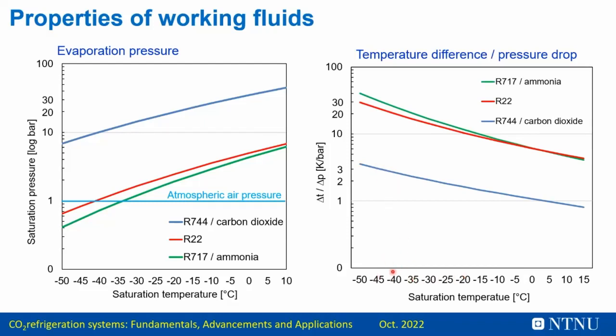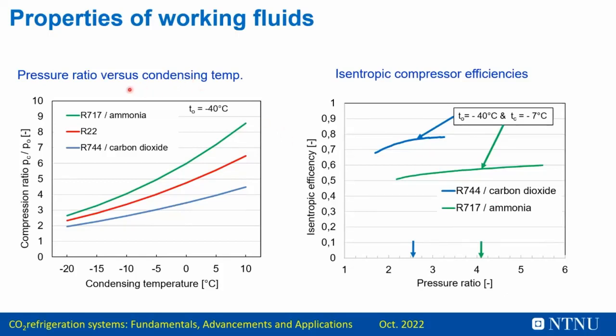While for CO2 you can see at these low temperatures 1 bar pressure drop is only 3 Kelvin temperature difference, which is very good if you want to have a uniform temperature at your evaporators. And the further up we come, the smaller this delta T becomes, which is a huge benefit. When we look at the pressure ratio versus the condensing temperature, we can see that the pressure ratio for a CO2 unit is much smaller compared to R22, which is even lower than for ammonia. And as we know, the pressure ratio has a major impact on the isentropic efficiency or the compressor efficiency. So we can achieve a very high isentropic compressor efficiency at a relatively low pressure ratio, which is the case for CO2 in most of the applications we are talking about.